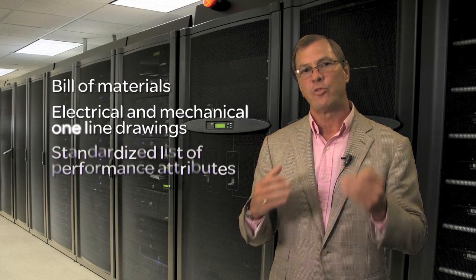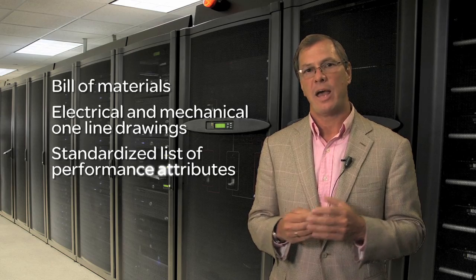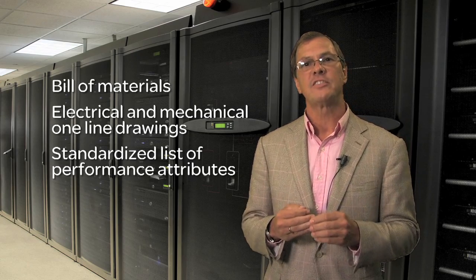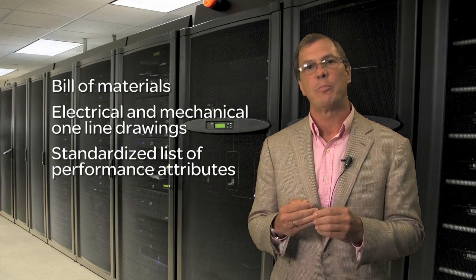A reference design for the physical infrastructure of a data center is a tested, validated, documented design package that allows the design to be reused across many different installations. When we talk about a reference design, some of the things that are included are detailed bills of materials, one-line diagrams, but beyond those standard CAD level documentation packages, we also have more information like system level performance, which can be assured by the design instead of what we typically do, which is try and roll up the performance of the individual components to determine the design performance. And this is a huge advantage.